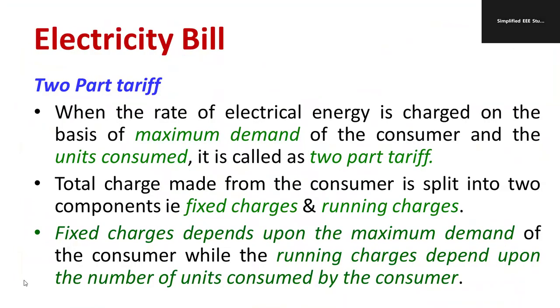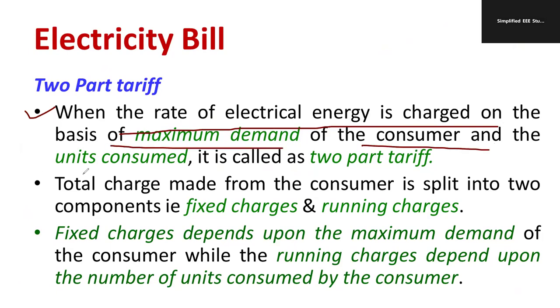Two-part tariff comprises of two components. One component is called fixed charge and the other one is called running charge. When the rate of electrical energy is charged on the basis of maximum demand and the number of units consumed by the consumer, the total electricity charge is going to depend on maximum demand as well as number of units consumed.